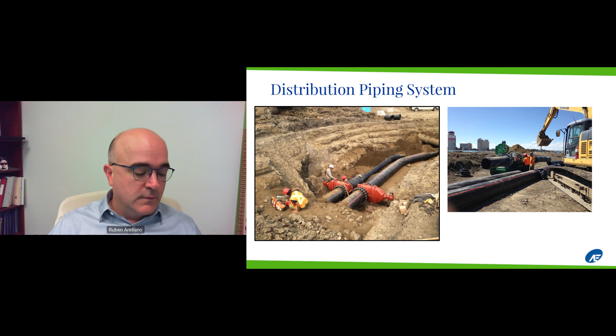Just a couple of sections. There's nothing too unusual that deviates from more standard civil design here. The DPS, or distribution piping system, is buried at about 2.8 invert from existing grade. We do put frost shield insulation on top of it, but the pipe itself otherwise is not insulated, as you might see with some other types of district heating systems.